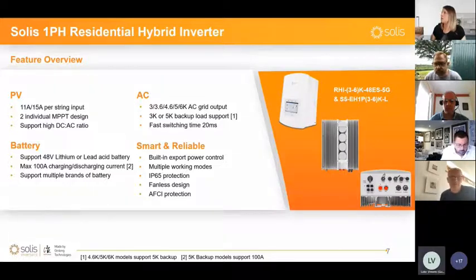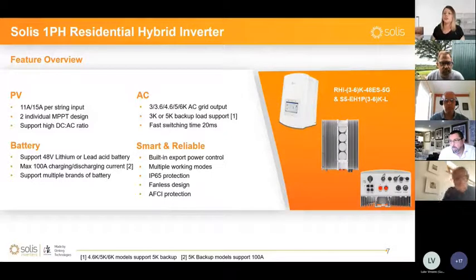What I can tell you about these, on the PV side, depending on the size, is that you can have either 11 amps or 15 amps PV panels per string input. All of these have 2 inputs with 2 individual MPPTs, and depending on their ratio, they have a quite high DC to AC ratio, meaning that you can install, for example for the 3.6, a little bit lower, but you can connect on the DC side to have a DC to AC ratio of over 1.7.